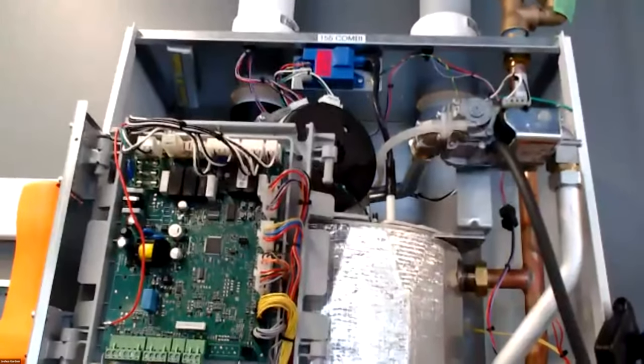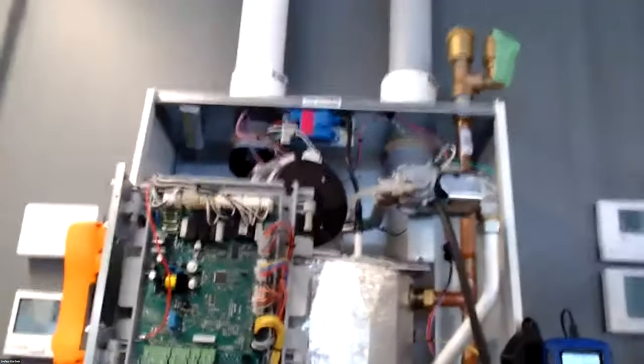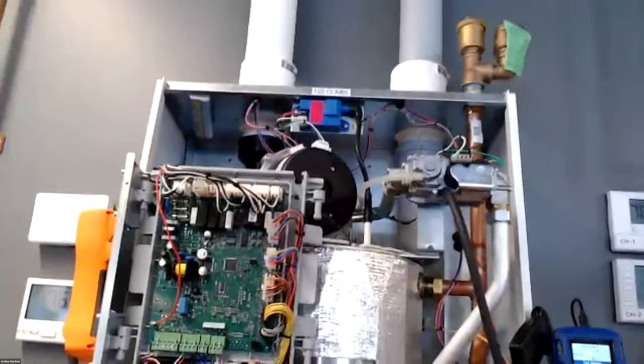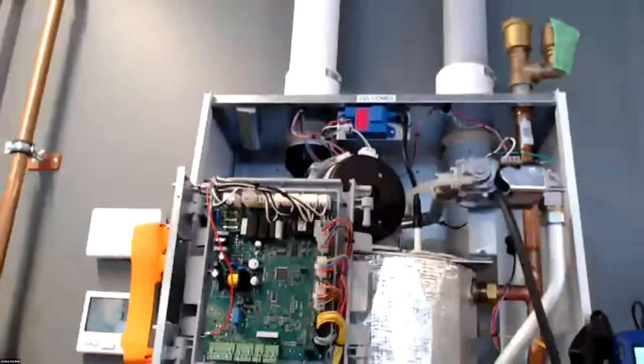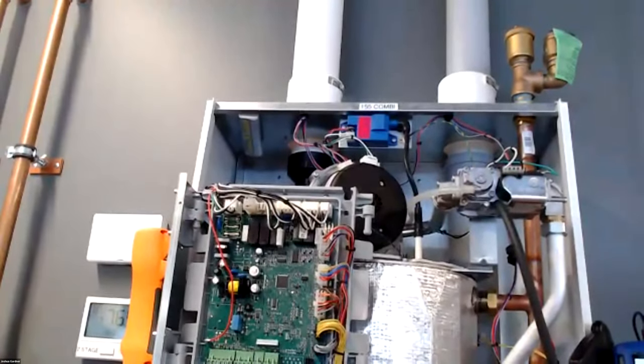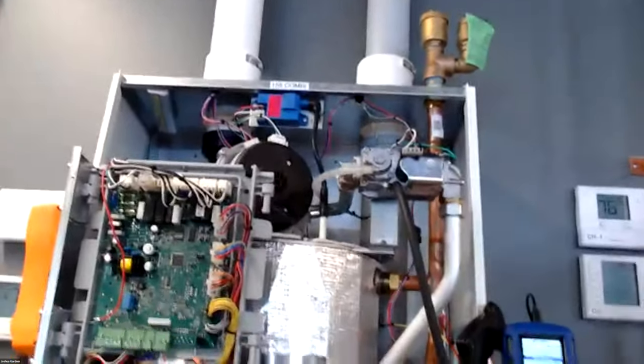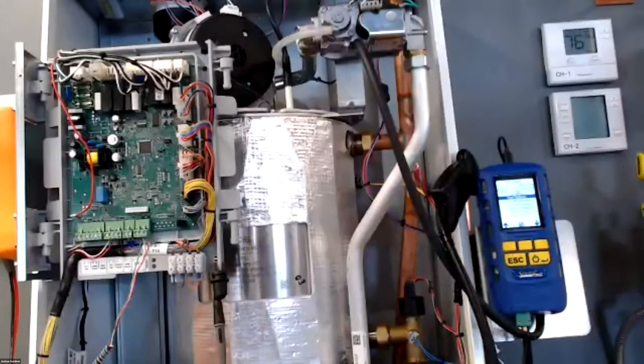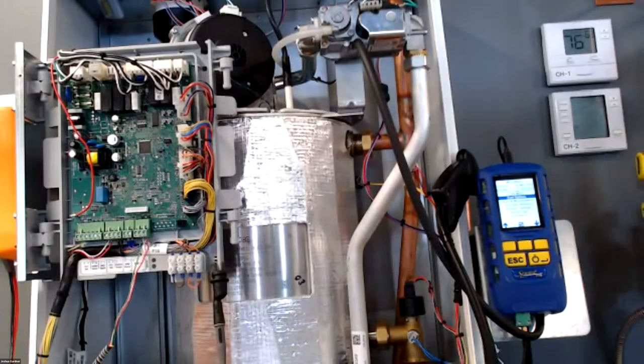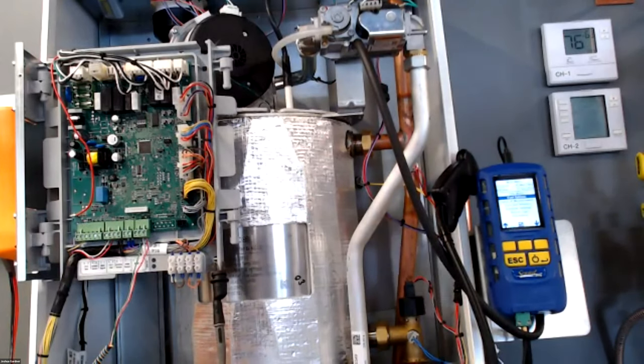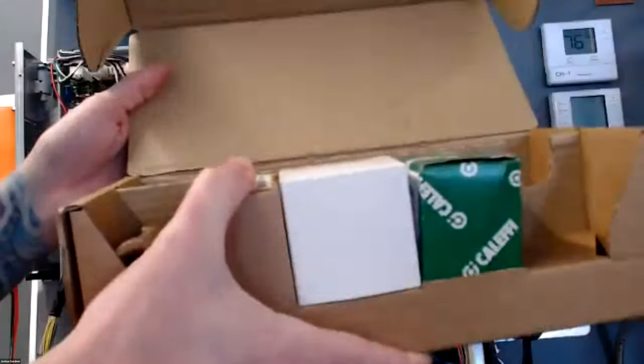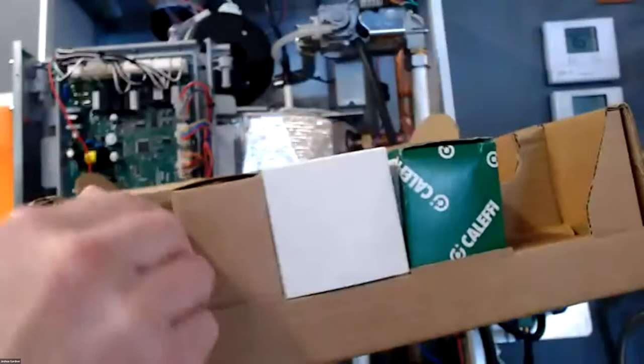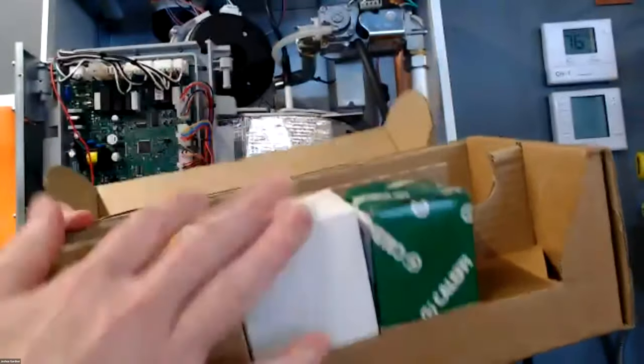Okay. So I guess we can go through the boiler, the wall hung, from top to down. So on top of the boiler, first you're going to get the boiler, you're going to open it up, and you're going to have paperwork, you're going to have a parts kit. Right here, it's going to have your air vent, it's going to have your fittings to make up the air vent, and the relief valve comes with it.